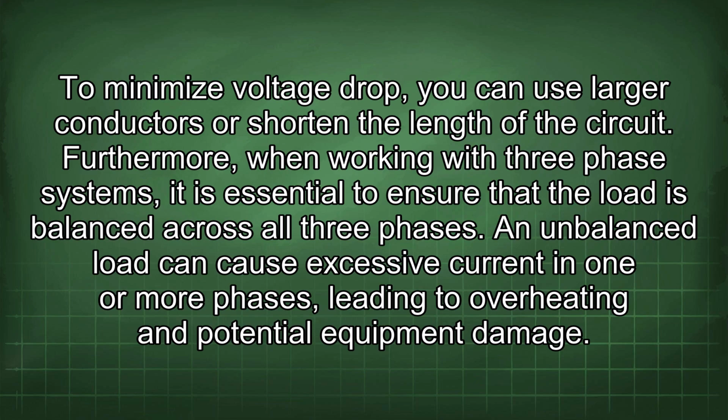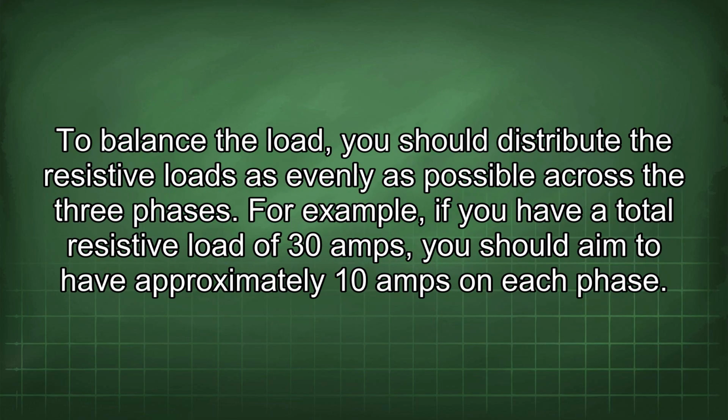Furthermore, when working with three-phase systems, it is essential to ensure that the load is balanced across all three phases. An unbalanced load can cause excessive current in one or more phases, leading to overheating and potential equipment damage. To balance the load, you should distribute the resistive loads as evenly as possible across the three phases.